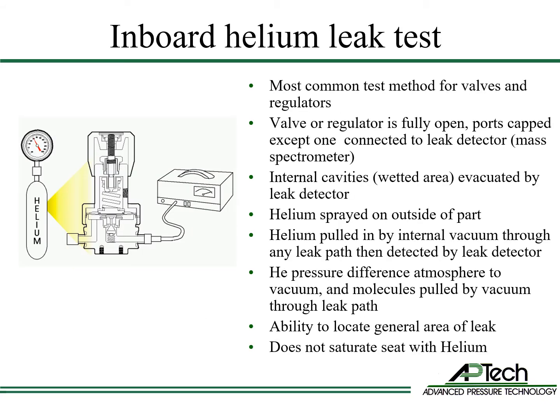Now let's review the specific leak testing methods and their relative merits. The inboard helium leak test is the most common test method. The valve or regulator is fully open and all ports are capped except one, which is attached to the mass spectrometer. The leak detector's vacuum pump evacuates the internal cavities to vacuum. Helium gas is sprayed around the part and into leak test ports. The differential pressure from atmosphere to vacuum pulls the helium molecules through the leak path. This method allows the test person to locate the general area of a leak, which is very useful for troubleshooting, and does not saturate the seat with helium.